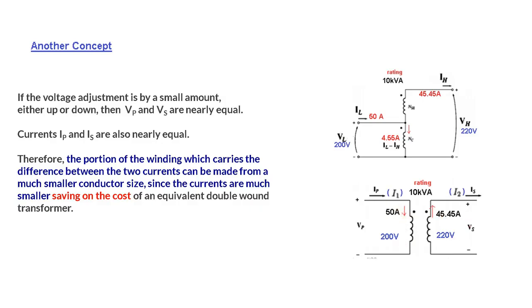This primary side will be carrying because if kVA rating is 10 kVA. So the primary current will be 50 ampere and the secondary current will be 45.45 ampere. If we connect this into this mode as an auto transformer then what is happening the current remains same primary current here the secondary current but current in this winding is reduced to only 4.55 ampere.